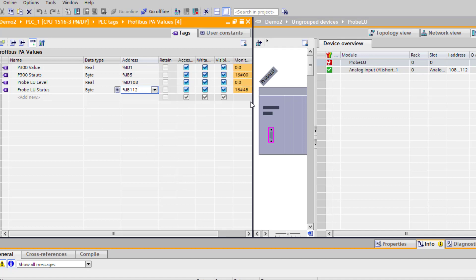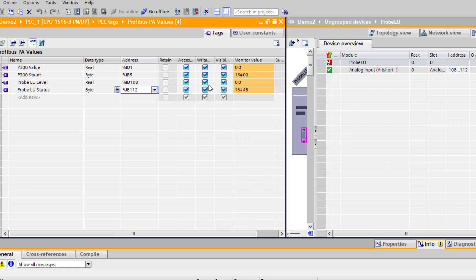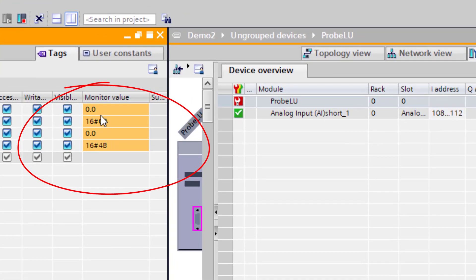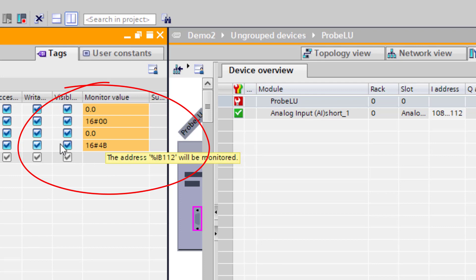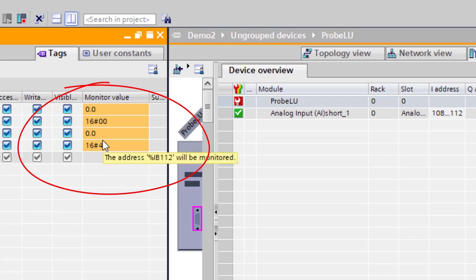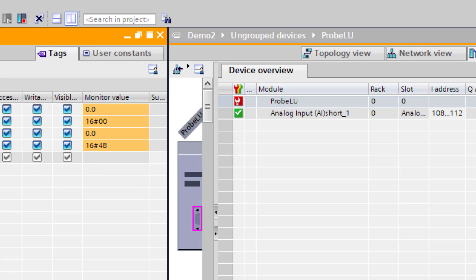So I can see this device here isn't physically connected, so your status byte goes to zero. That's a good feature in status byte: straightaway zero, status byte stays by, it's the device is physically not there. My pro values gone to a level of zero, and I can see from a status byte 4B, if it's healthy that will be hex 80. 4B is indicating an error.